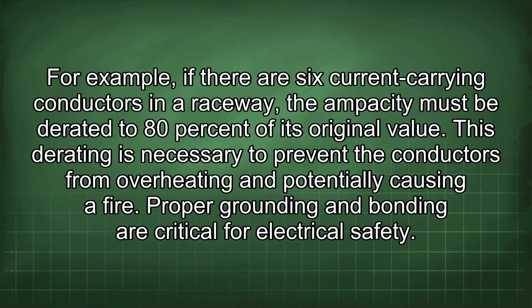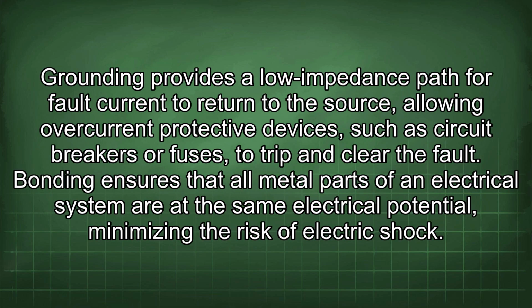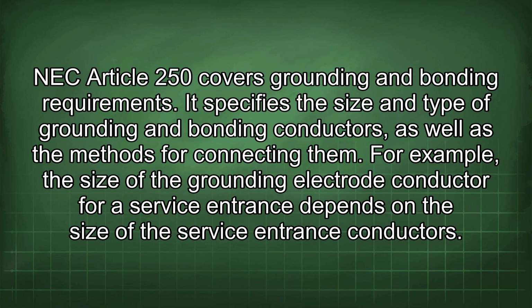Proper grounding and bonding are critical for electrical safety. Grounding provides a low impedance path for fault current to return to the source, allowing overcurrent protective devices such as circuit breakers or fuses to trip and clear the fault. Bonding ensures that all metal parts of an electrical system are at the same electrical potential, minimizing the risk of electric shock. NEC Article 250 covers grounding and bonding requirements.